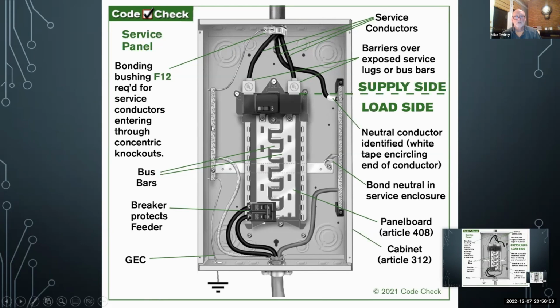This terminal is actually touching the can. I'll show you a slide of a sub panel in a minute. If it's a sub panel, then this one's bonded. Okay. Now in this panel, the neutrals and equipment grounding conductors are required to be bonded together. They're all tied together because this is a service equipment panel. So you can tie the neutrals and the equipment grounds to either one of these bars in this panel.